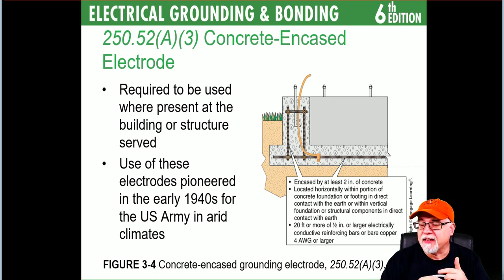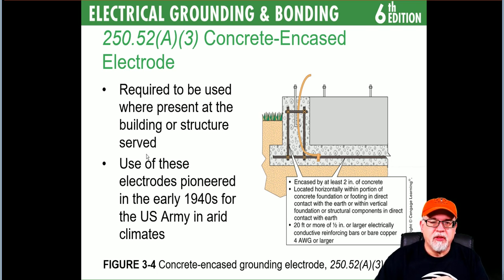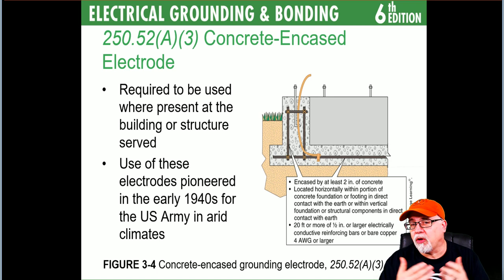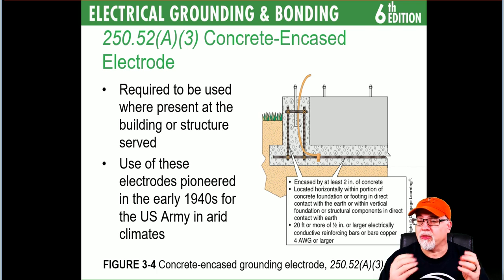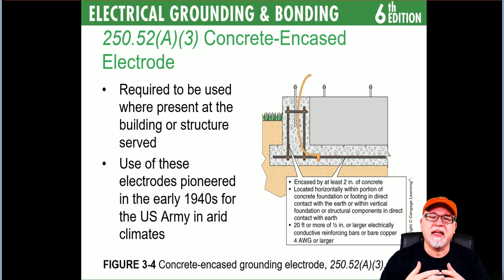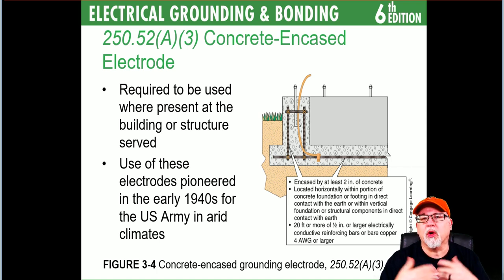As an electrician coming in after the fact, you need to consider whether somebody made connection to it and whether the timing was right to get that four-gauge copper down to the concrete encased electrode. This was used all the way back in the early 1940s — the U.S. Army used it in dry climates like Arizona. Concrete retains a lot of moisture, and the concrete encased electrode works in conjunction with the rebar. Together they are the electrode — it's not just the rebar.